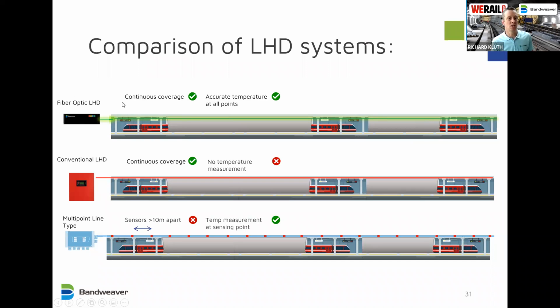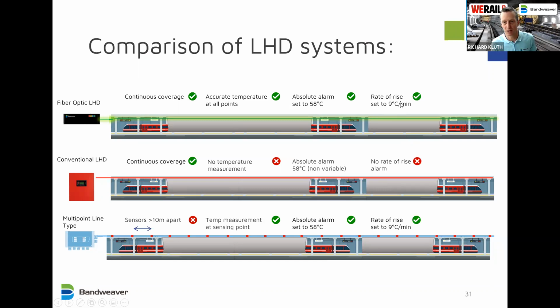The fiber optic linear heat detector can measure temperature, so you have accurate temperature at all points. The conventional cannot, the multi-point does. So measuring the temperature enables you to have the smart alarm functionality. And the smart alarm functionality, as we said, is the configurable absolute alarm, in this case set to 58 degrees C. The conventional one, for this example, we're using 58 degrees C, but it's not variable. It would be selected by the material selection. The rate of rise of the multi-point and the fiber optic is 9 degrees C. The copper-based LHD doesn't have rate of rise, and the deviation alarm of the fiber optic and the multi-point 9 degrees, again no rate of rise with the conventional.